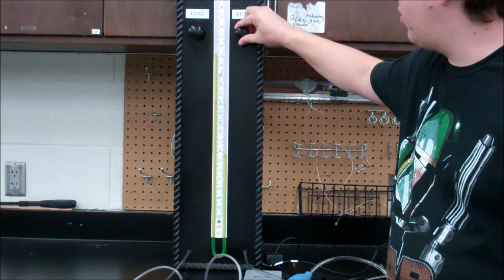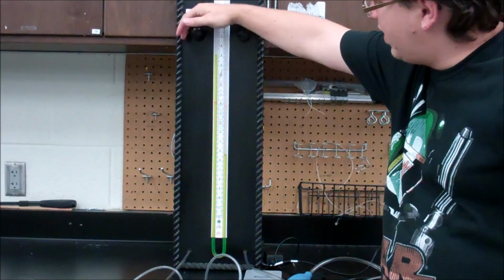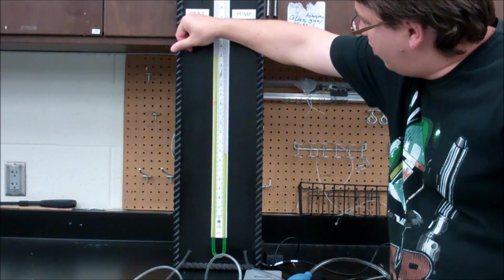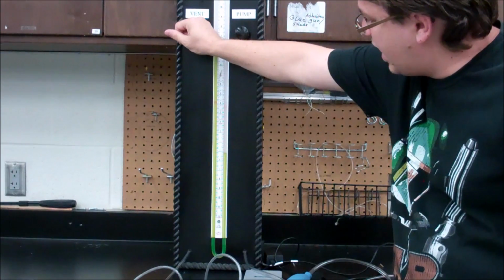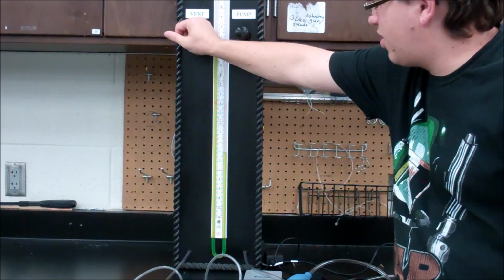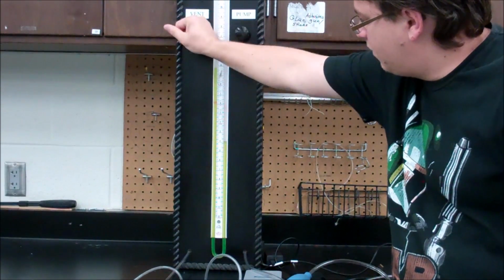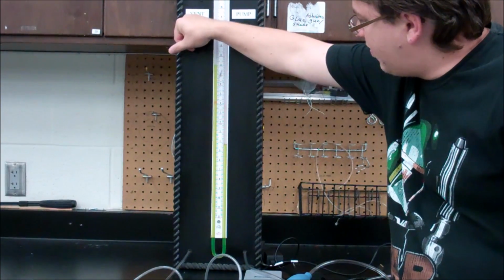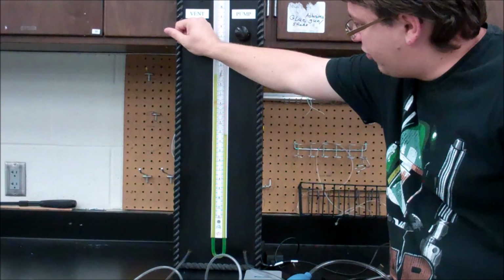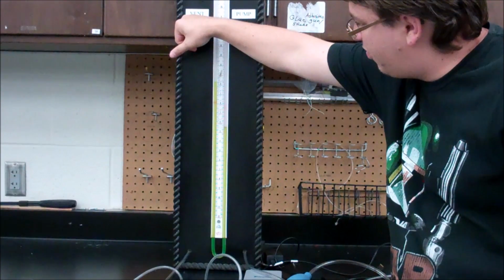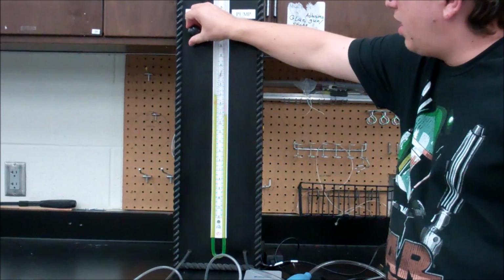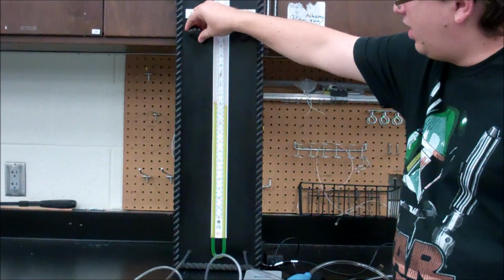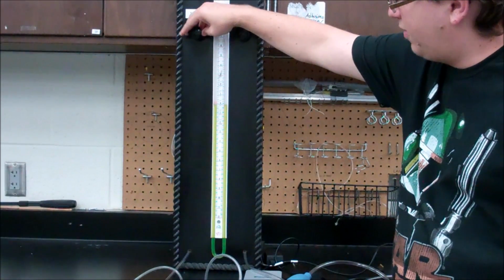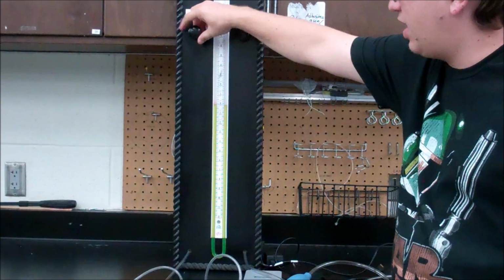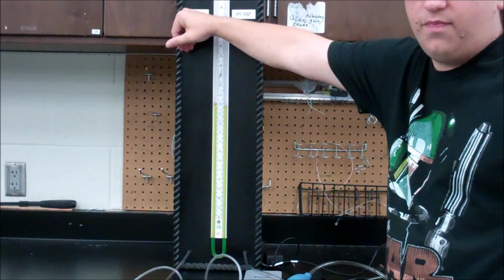And then what you're going to do is take a measurement, open the vent a little bit to let it go down a little bit, then take another measurement, let it go down, take another measurement, and keep on doing this till you get to 10, with the hose connected to the positive side of the pressure transducer. Now you're going to want to make sure you include a zero differential point. You must have zero differential as one of your measurements.